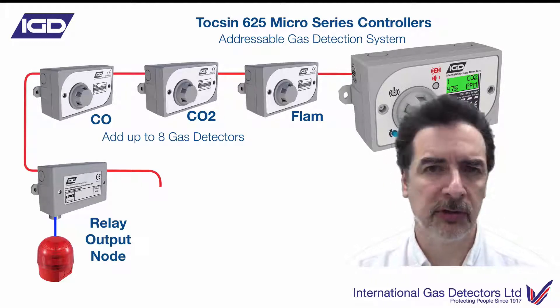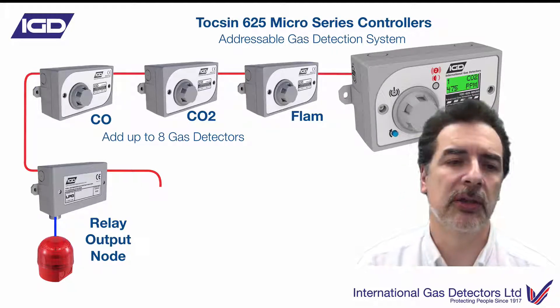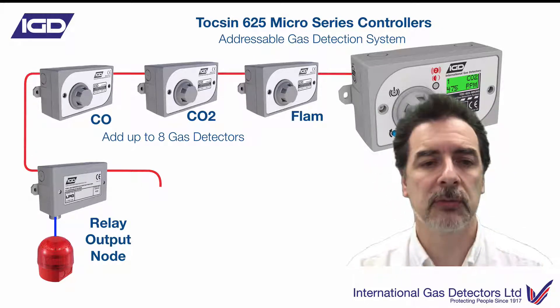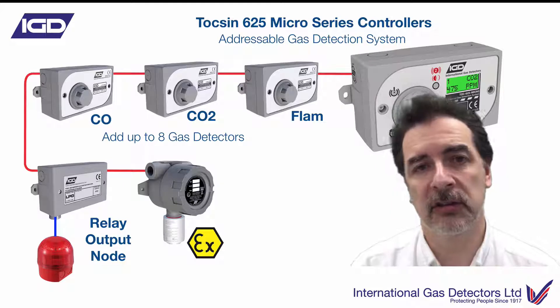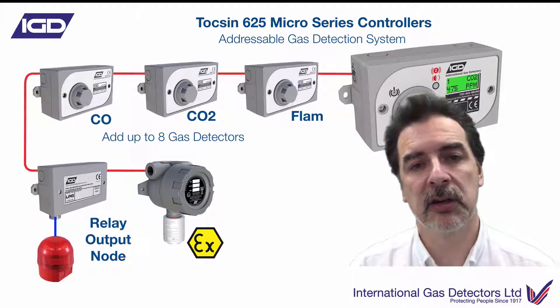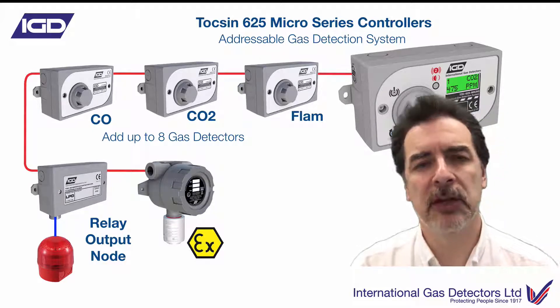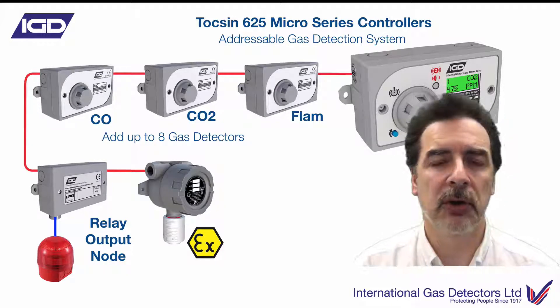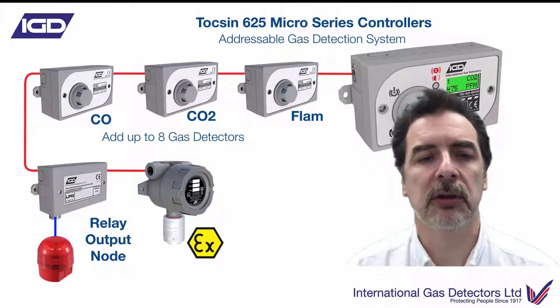You can add relay output nodes onto the system if required — maybe for a beacon sounder, dropping a gas solenoid valve, or interlocking with ventilation. You can do that with the relay output nodes or use the relays on the panel, whichever is preferred. You've also got the ability to connect ATEX gas detectors if needed. So if this was a restaurant with an LPG tank outside, you'd have ATEX in the tank area and normal flammables around the restaurant. All of those small applications where you don't want a full-size controller, you can do it using the Tocsin 625 Micro.